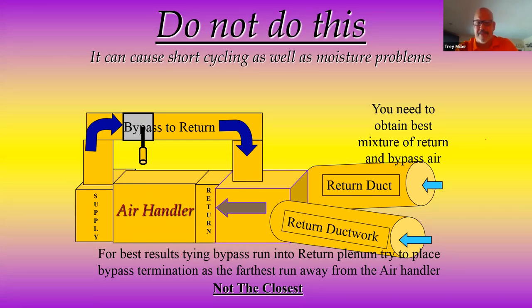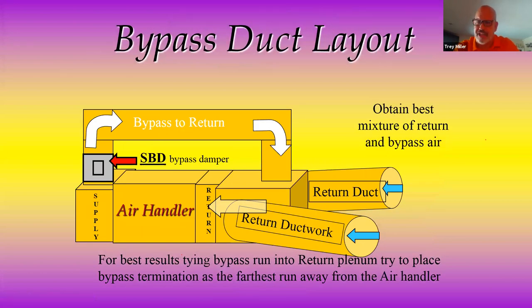And therefore, we've maintained the bypass, we've restricted too much bypass air from going through, we've eliminated the sweating, and we've made sure we've got great mixture. This is the way I would love to see it if we're doing new construction or if we have the opportunity to do some retrofit ductwork: tying my bypass at the back of the plenum, building the majority of the return static on the returns themselves. Therefore, I'm filling in what the returns are not producing. Now, that is another neat thing about the SBD, because the SBD has opposed blades, which is going to create turbulence. The turbulence is going to force the mixture, which allows us to not flood the unit with too much bypass air, making sure we get the right amount of bypass, only filling in what the unit is pushing.